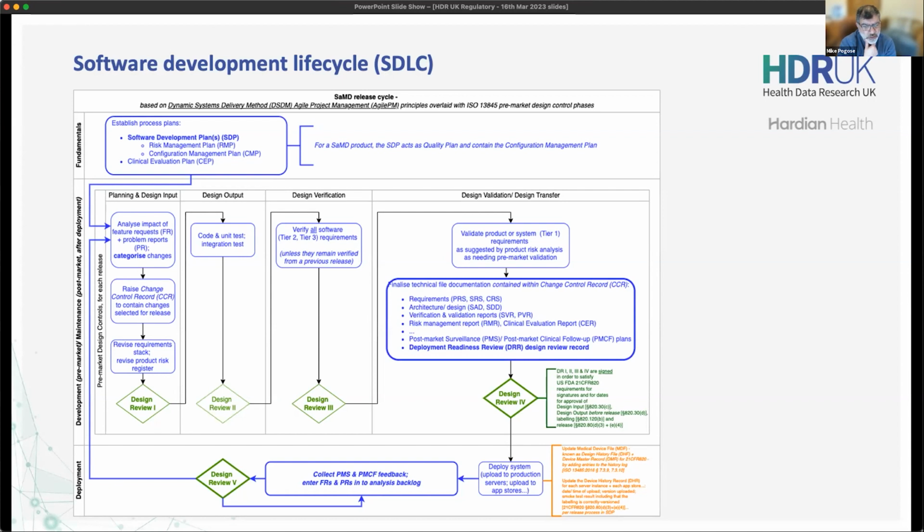And as we said, the unit acceptance criteria, do you need to peer review some of it? Do you need to enforce style on it? Do you need to run unit tests? Design verification, then look at partial regression. What has changed? What do you need to regression test? What's new that you need to test for the first time? Design validation. Have you caused anything? And the answer could be no, that requires revalidation with intended users.